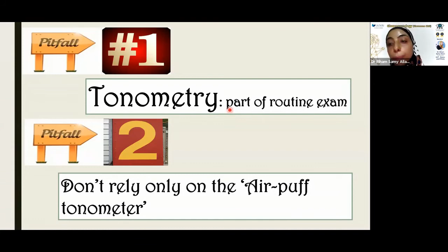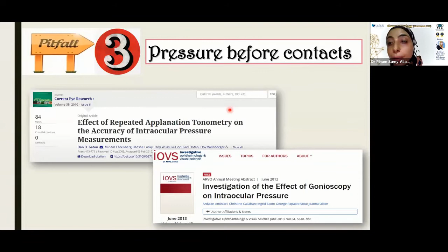Do not rely only on screening tools like the air puff. The air puff is only a screening tool. When you spot a high pressure with the air puff, you should repeat it with Goldmann applanation tonometry. Pressure before contact: please measure the pressure before anything contacts the eye of the patient. Just like Dr. Nader mentioned, gonioscopy is part of the routine examination. You should not measure pressure after you perform gonioscopy, or you will get a falsely low estimate of the intraocular pressure because of the massage effect of the gonioscopic lens itself.